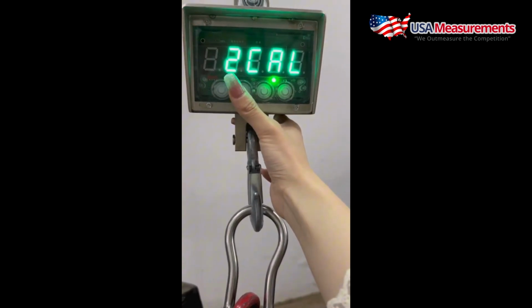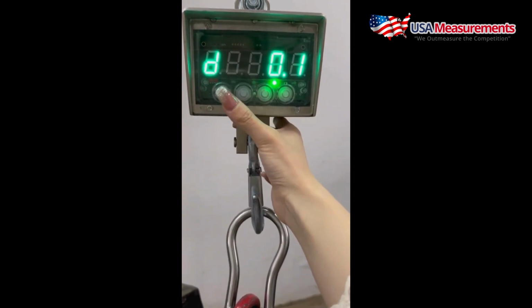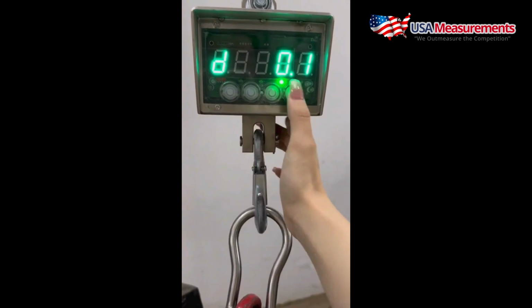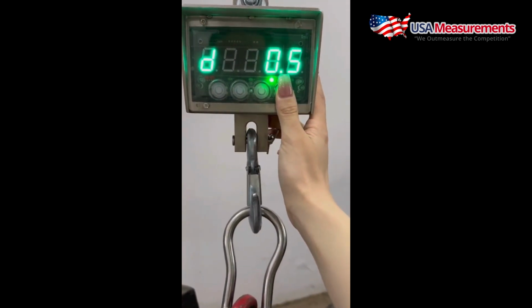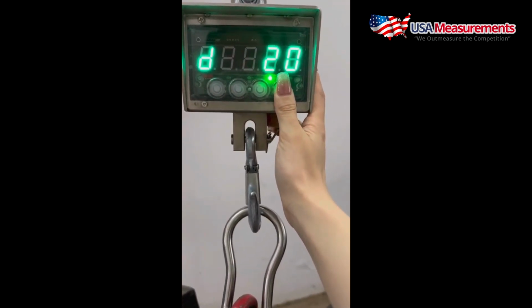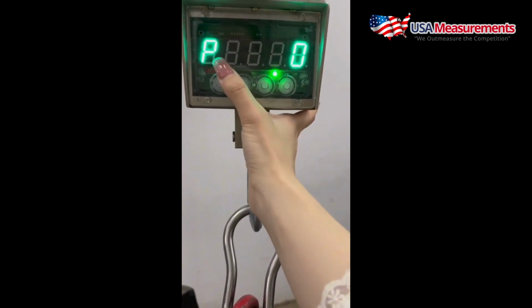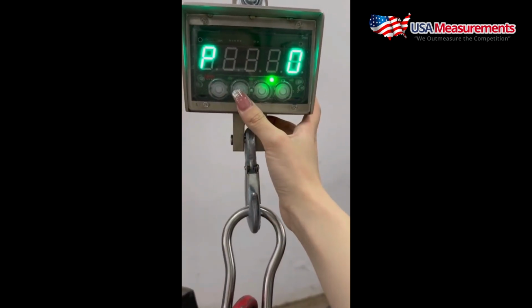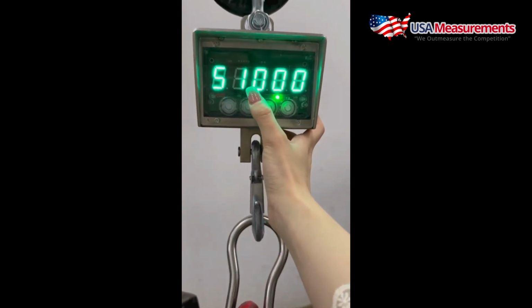With the password entered, press the function key again to confirm. Next, set the division or readability. We'll set it to 0.1 kilograms, then press function to continue. Confirm the 0 reading is correct, then continue to set the capacity.